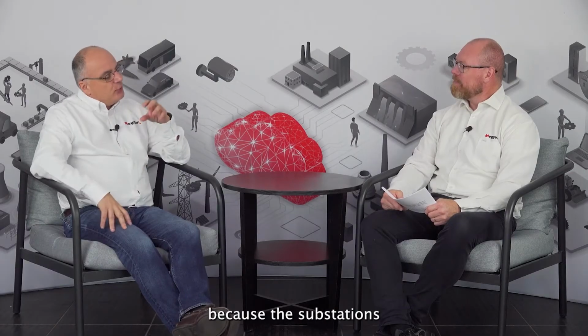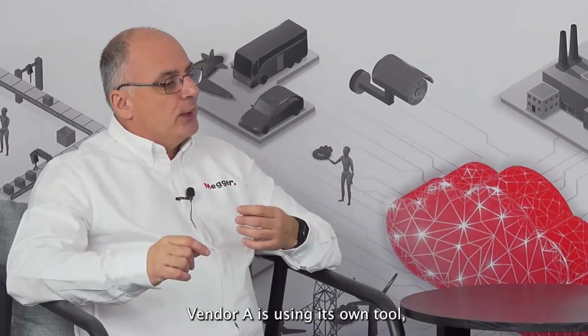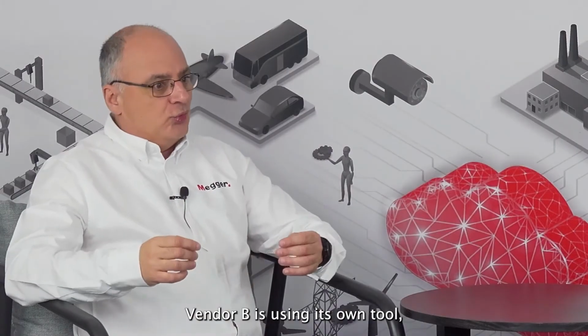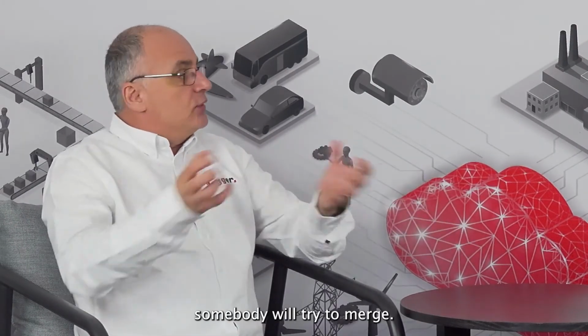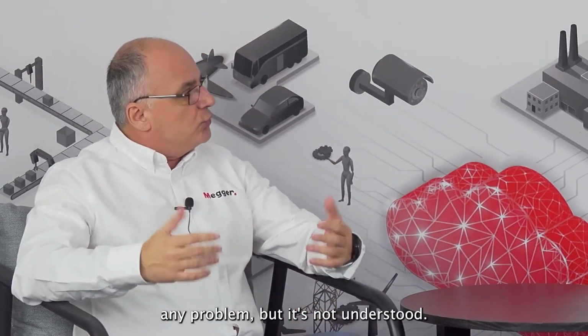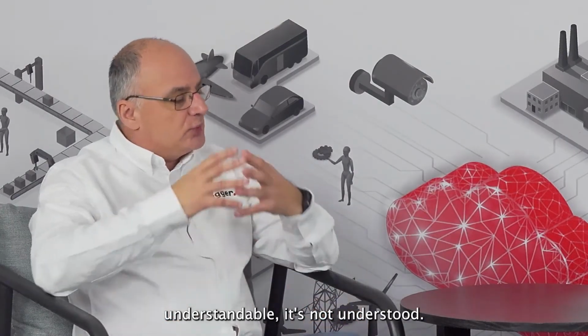But it's not because IEC 61850 is bad. It's because the substation has been engineered in the wrong way. If they had followed the top-down engineering process, for example, you would go through this test without any problem, because you do the substation, you first make the SCD file, and you set all your relays according to what's written in the SCD file. If you do partial engineering, vendor A is using its own tool, vendor B is using his own tool, and they don't care about the other tools, and then at the end somebody will try to merge. That is where things will not work. But if you use one master tool and you do the top-down engineering, there will not be any problem. But it's not understood. I don't know how to make it understandable. And that's where you get into interoperability problems, as you hear a lot about.